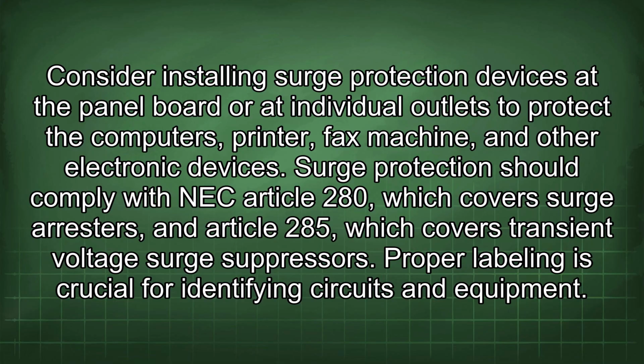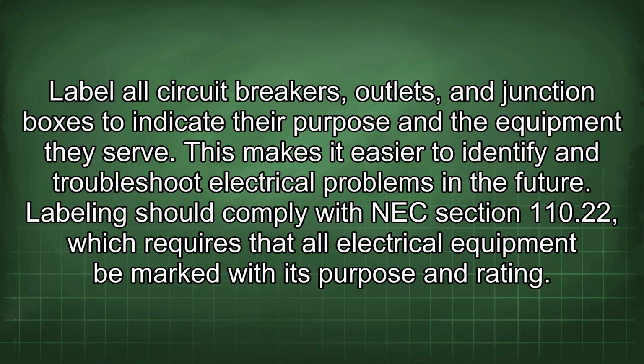Proper labeling is crucial for identifying circuits and equipment. Label all circuit breakers, outlets, and junction boxes to indicate their purpose and the equipment they serve. This makes it easier to identify and troubleshoot electrical problems in the future. Labeling should comply with NEC Section 110.22, which requires that all electrical equipment be marked with its purpose and rating.